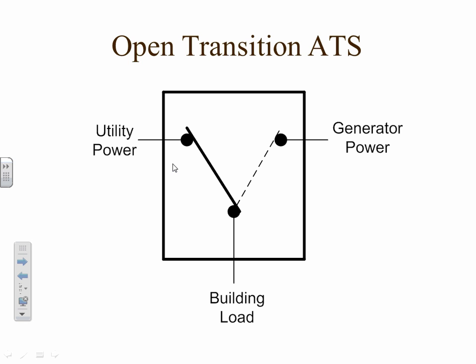Well, the first time delay is a time delay on start, and it's only for like 2 seconds to make sure the power is really out. Because on a larger set where you have that instance I just talked about, you don't want to be slamming that big diesel starter on a 20-cylinder unit home every 2 seconds. So if it's gone for 2 seconds, we say it's real. Start the generator, and then the signal goes in. That's the first time delay, on start.